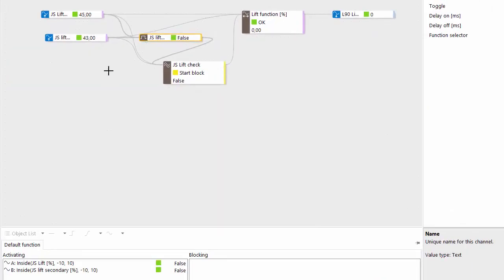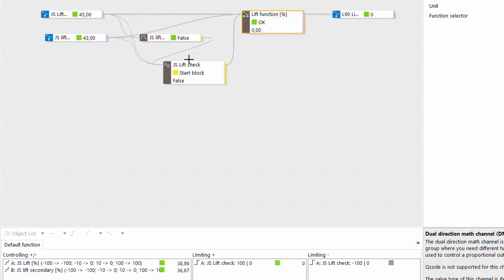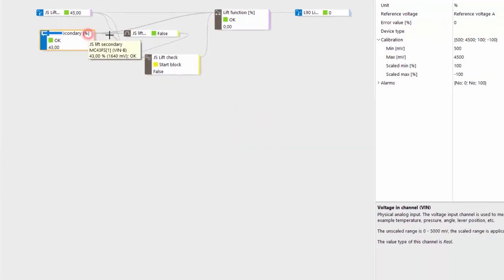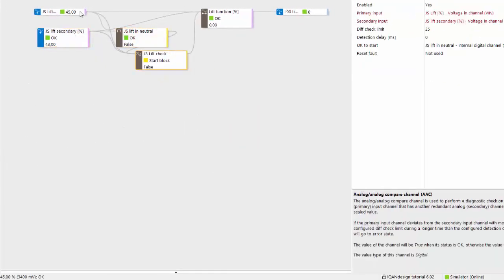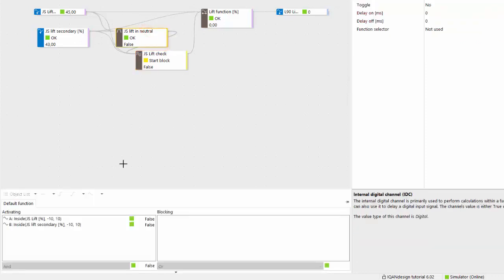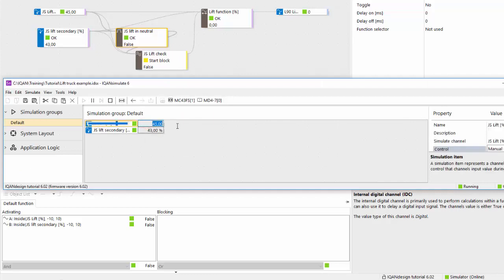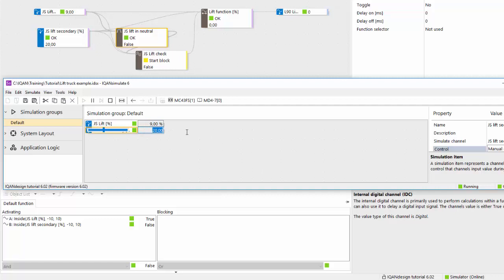And we can simulate. So in our simulator here we can see the joystick lift check is in start block, so we get no output here. Just look at the values here we see, so it's 45 and 43, so joystick lift in neutral is false. And if you try to bring this a little bit closer to the center position here, still outside of the deadband. Now we see both of them are within neutral and joystick lift neutral is ok, start block is ok, so we can start to activate here and give some value and we get activation on the output.